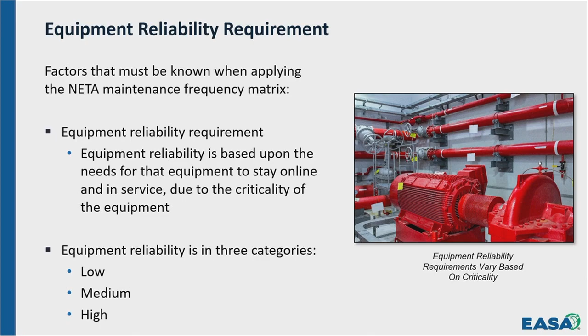But there are a couple of documents. NETA has some guidance for maintenance time frames, based on criticality and how important something is, and time. There's a maintenance matrix you can apply factors to for a time-based approach, whether it's low, medium, or high reliability, and that helps you figure out how often you should do something. If it's critical, like a fire pump, that's critical. If it's an exhaust fan for the shop, maybe not as critical as one for the restroom, which is more critical. So apply those factors and it'll help you.